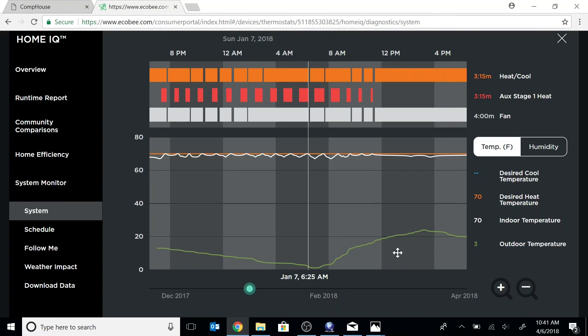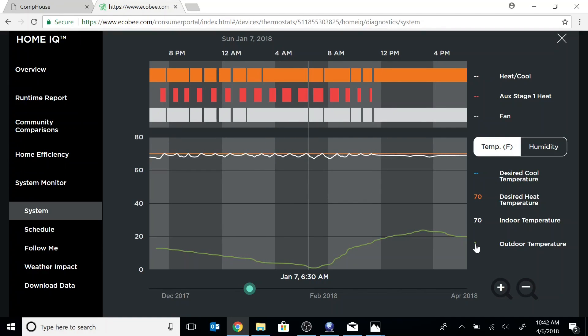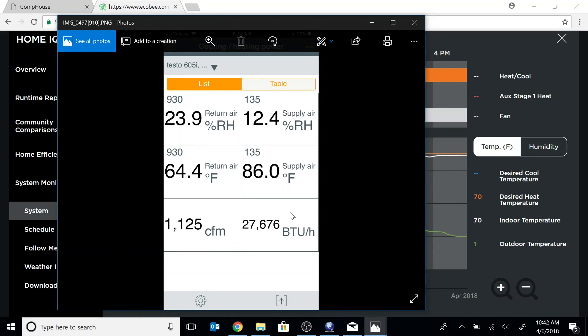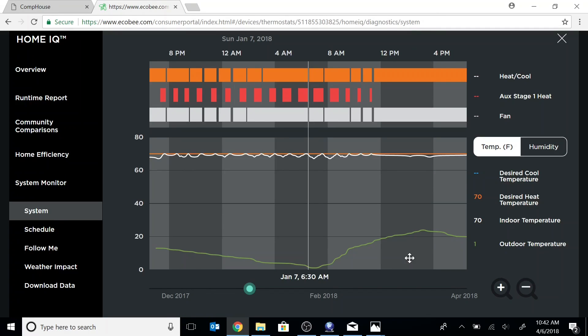Fast forward to January 7th at 6:25 AM — before people are really getting up, no sun, no solar gains, no internal gains. You can see that my system turns off at one degree outside after electric heat ran with the heat pump. At one degree, it turned off. With the electric heat operating and the heat pump at one degree, we are essentially at 27,000 BTUs. So that kind of proves how liberal the heat load calculation can be.